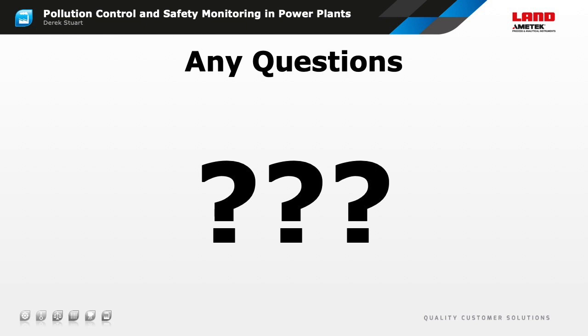Okay, thanks for that. Moving on to some more questions coming in here. You briefly mentioned a continuous parametric measuring system. Please explain in more detail. Yeah, that's taken care of with a US EPA rule. In general, PM-CEMS has to be calibrated by correlating its output to the actual dust concentration measured by a reference method. And that's true regardless of whether it's an opacity monitor or a scattered light device of some sort. These correlation tests have to follow some quite complicated protocols and involve extensive testing by a skilled test team, which makes the correlation test quite expensive.